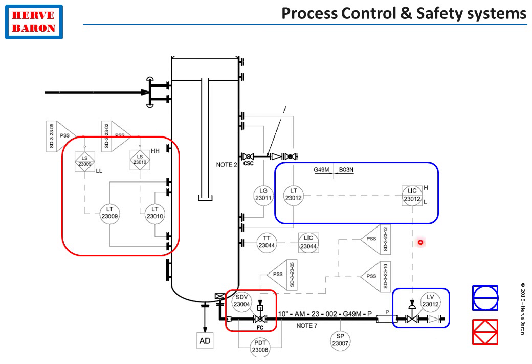As you can see, the process control system instruments, shown in blue, and the process shutdown system instruments, shown in red, are different instruments. Each system has its own instruments and controllers, so that the process shutdown system serves as a protection — and backup — in case of failure of the process control system. They don't share any instruments.